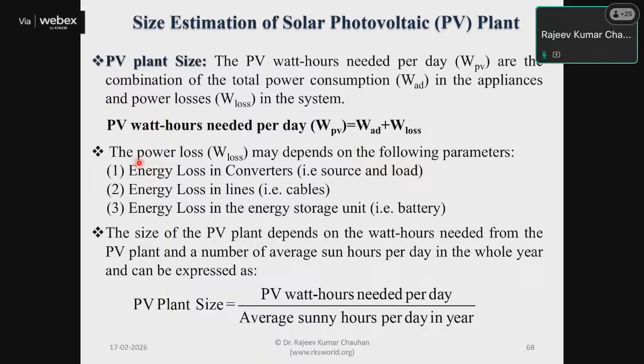The losses may include energy losses in the converters at the source and load end, energy losses in the lines and cables, or energy losses in the energy storage unit. As I mentioned, the battery bank has its own electrical systems, so if you feed 100 ampere-hours into the battery, you cannot extract the same amount back to supply it, because of internal circuit losses. So those losses are also considered in these system calculations.